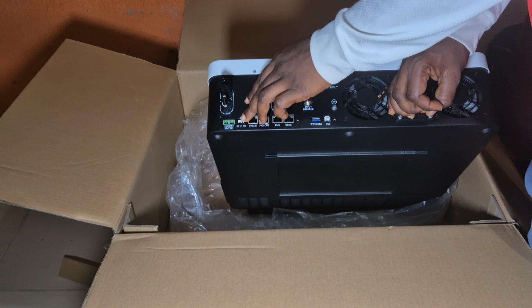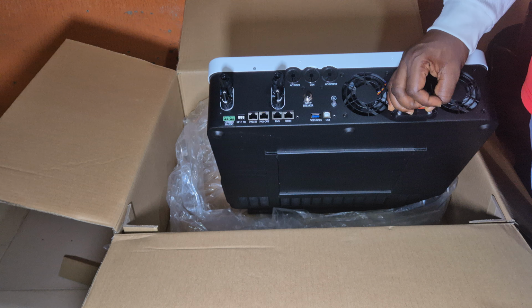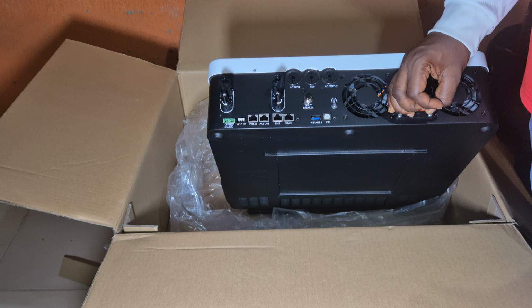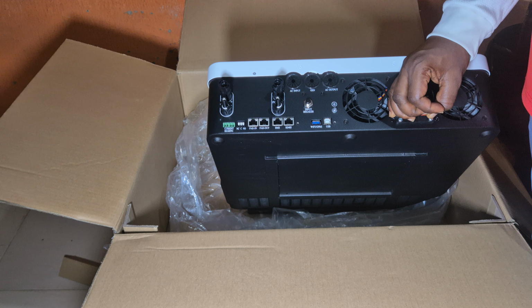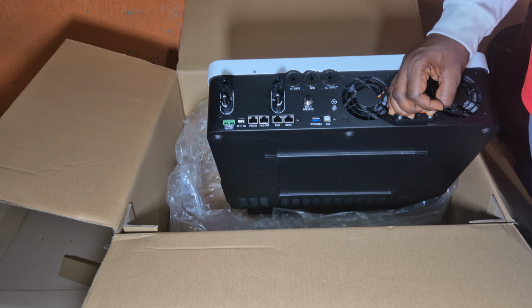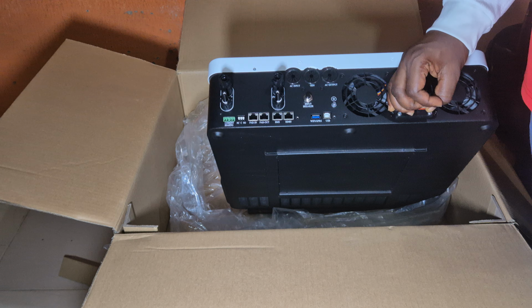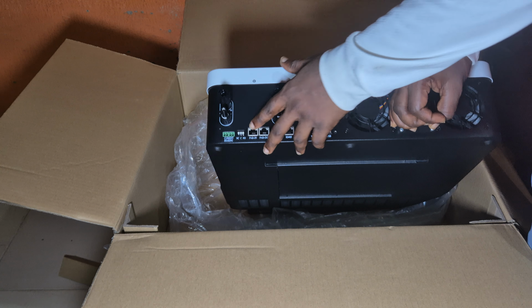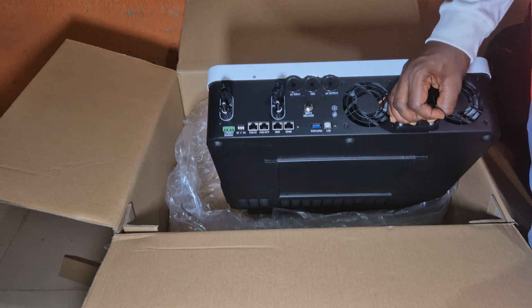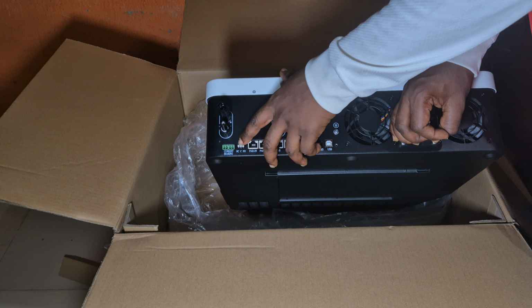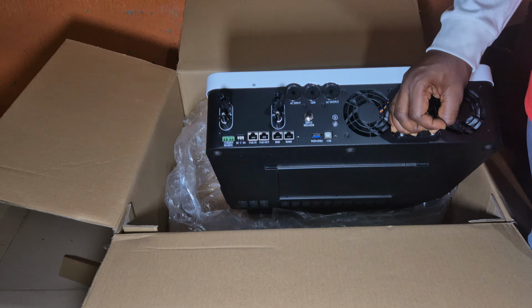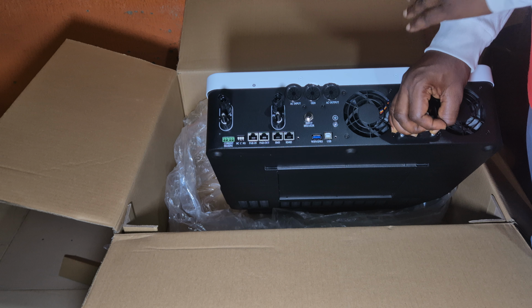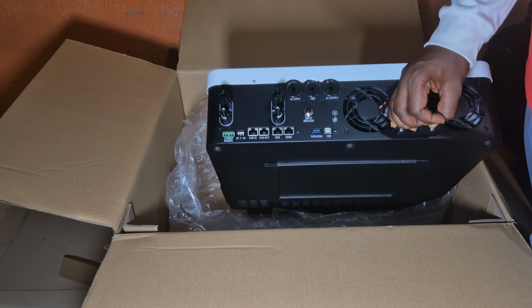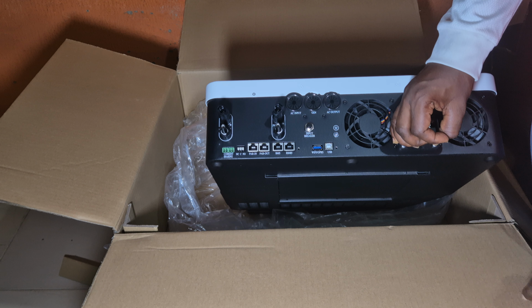What do you do with this? This is where you connect your inverter to some sort of external contactor, or some sort of shunt. Maybe you want your inverter to trip when certain conditions are met, to carry out some external command on external devices. A very good example is a shunt, and that's what I'm going to use this port for. I have an auxiliary shunt added to my circuit breaker, and I'm going to connect that shunt to this point in case the inverter gets to a certain condition. I'm going to determine later the inverter should trigger that shunt to trip, to close, so that I'm safe and the entire system is safe.